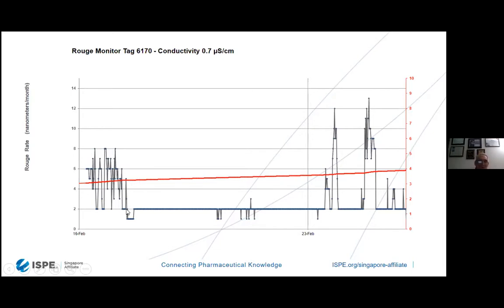Over here, at this point, you can see instead of running between 4 to 5 nanometers, all of a sudden we're below 2 nanometers. And the interesting issue is why? Well, it's very simple. We open up the valves to the points of use to fill up the vessels. And when you fill up the vessels, the contact time, the residence time of the water against the piping is lessened, because I'm producing the WFI water, it's sitting in storage, and it's going out to the point of use. It's not recirculating in the same piping 24/7.